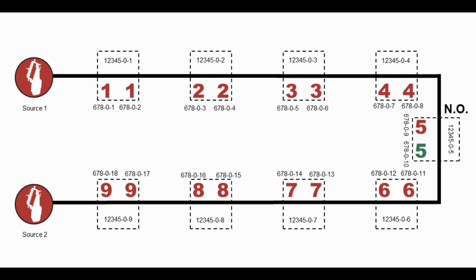Also record the cable designations of the normally open and normally closed cables on the normally open transformer. Because each installation is unique and standard utility practice varies by utility, a system example is used here to illustrate the recommended system planning. Use the GIS export to fill out a system plan. A sample completed system plan can be found on page 28 of the written instructions. Confirm the accuracy of the system plan after arriving at the installation site.